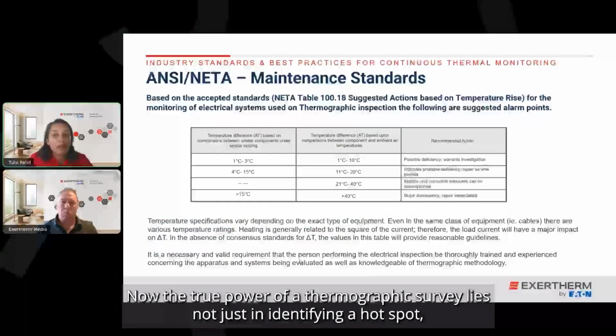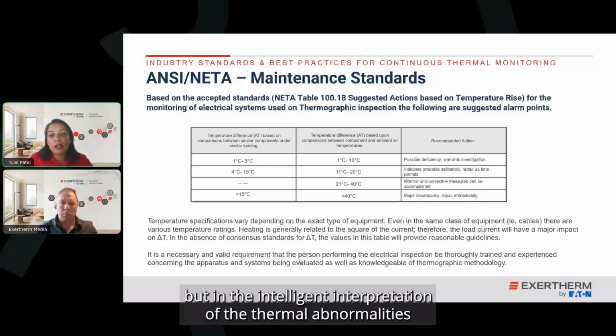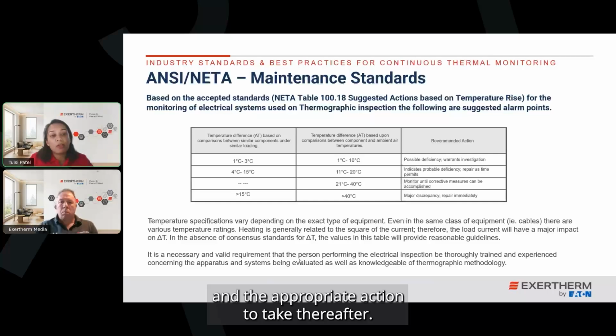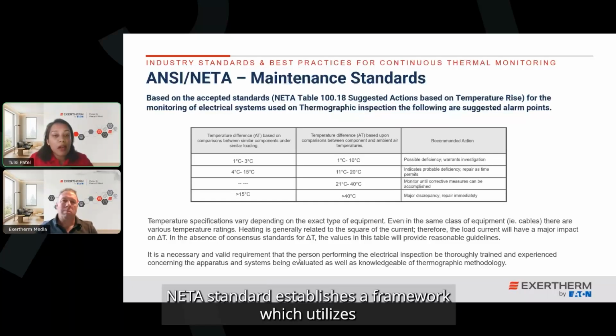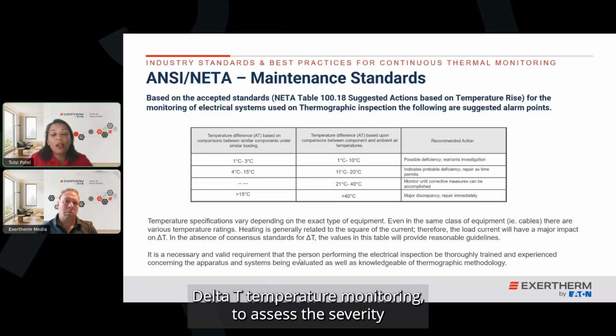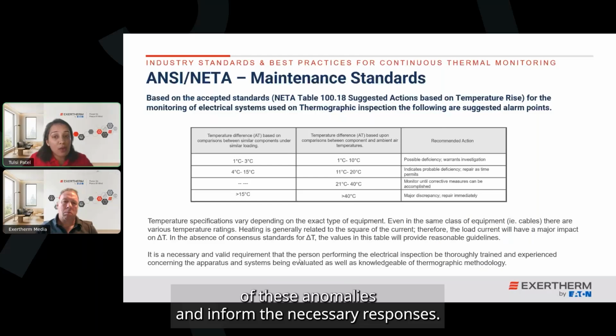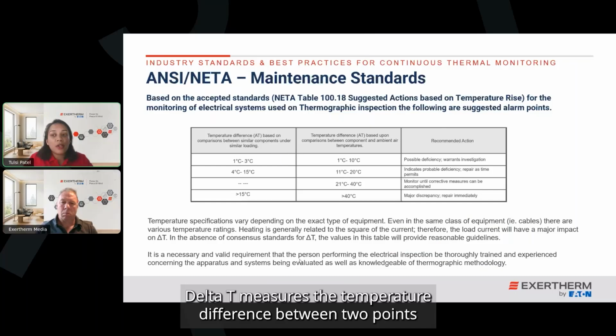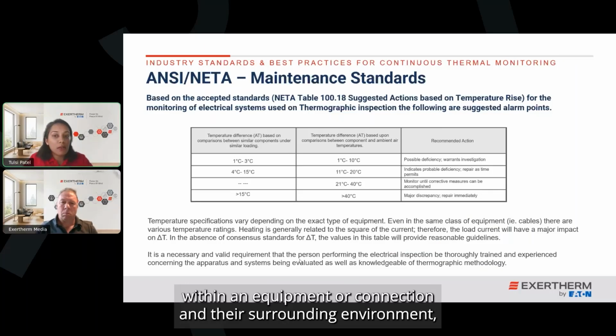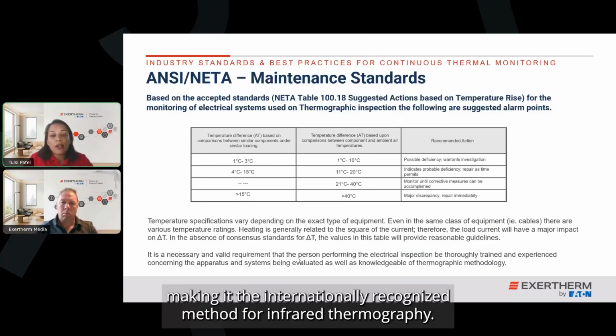Now, the true power of a thermographic survey lies not just in identifying a hotspot, but in the intelligent interpretation of the thermal abnormalities and the appropriate action to take thereafter. NETA standard establishes a framework which utilizes delta T temperature monitoring to assess the severity of these anomalies and inform the necessary responses. Delta T measures the temperature difference between 2 points within an equipment or connection and their surrounding environment, making it the internationally recognized method for infrared thermography.